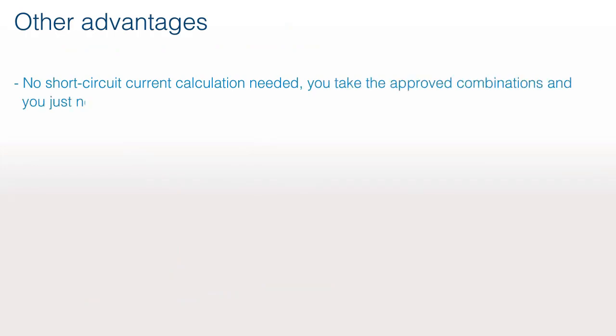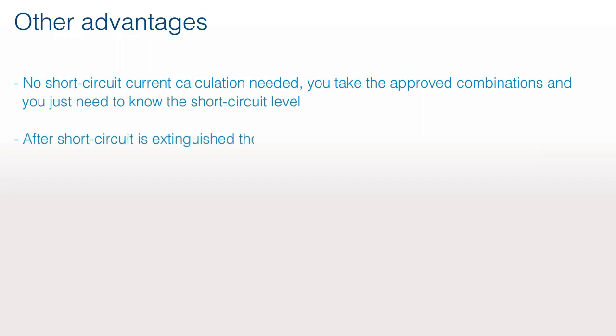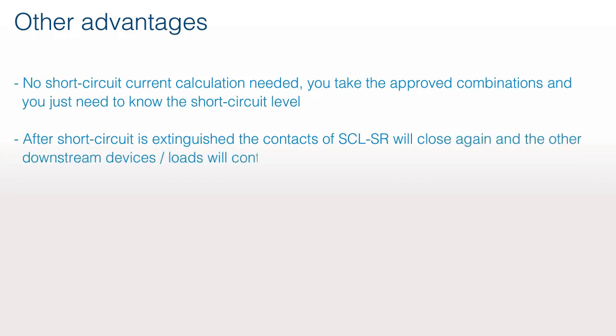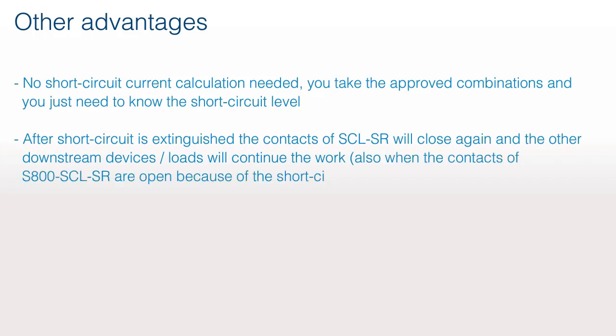Other advantages. No short-circuit current calculation needed. You take the approved combinations and you just need to know the short-circuit level. After short-circuit is extinguished, the contacts of SCL SR will close again and the other downstream devices or loads will continue to work. Also when the contacts of S800 SCL SR are open because of the short circuit. This means service continuity and no downtime.